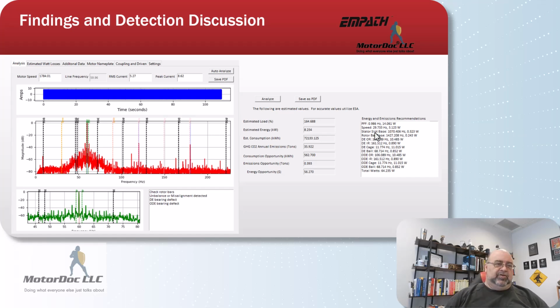We also developed an algorithm based upon historical data and a bunch of other stuff off of a single phase of current. We can estimate the actual watts losses. It's not as accurate as, say, the EMPATH is with both voltage and current, which is extremely accurate. But that conversion allows us to identify small changes in watts, which would be indicators for things like lubrication well ahead of any other technology. 1 watt changes, even 10 watt changes will not be picked up with vibration or ultrasound. Probably why they don't have us on the P to F chart, because we're so far to the left they can't keep up. And it wouldn't help their marketing.